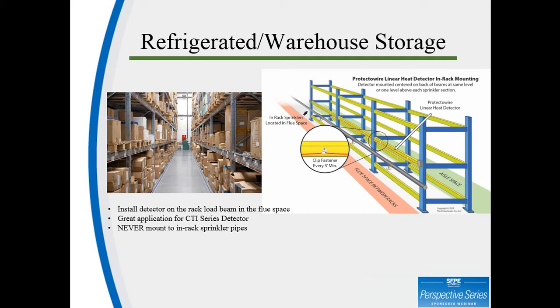We do not recommend putting the detector on in-rack sprinklers. Many of these warehouses use double interlocked pre-action systems. And if a pallet or box or something similar falls out of a rack and hits the sprinkler pipe and damages a standard digital linear heat detector, you would have a short on your detector and a low air condition in your pipes, causing water to flow despite there being no fire.